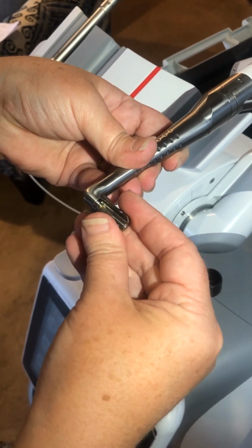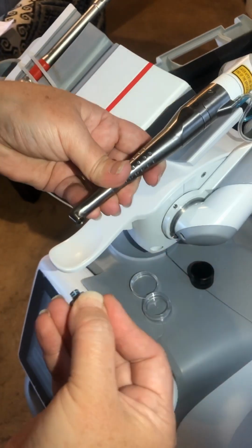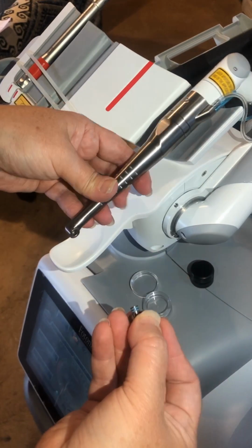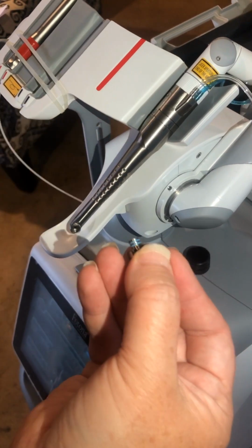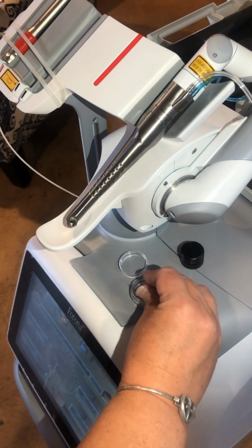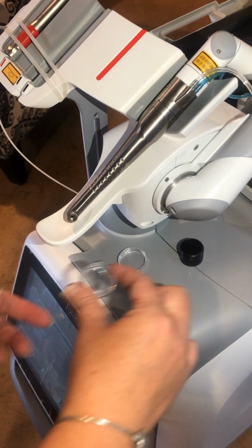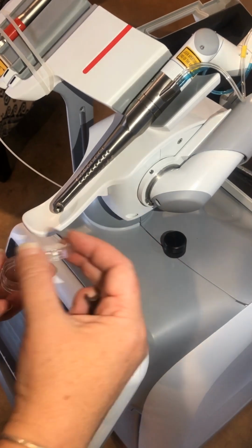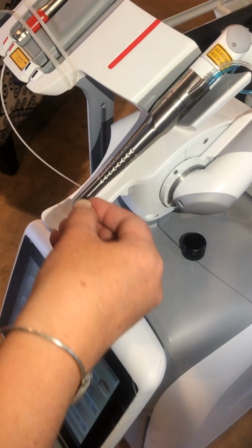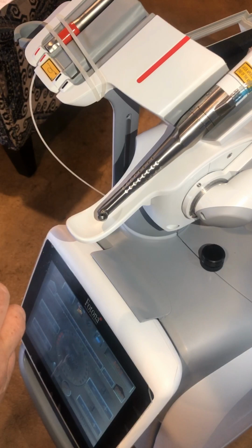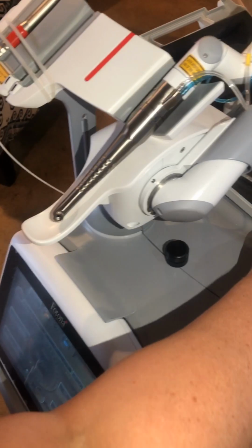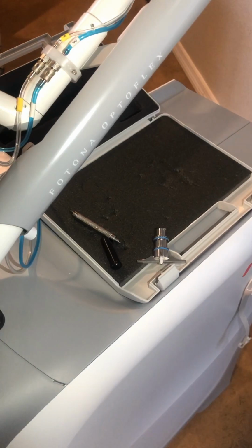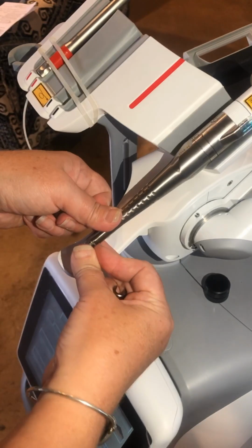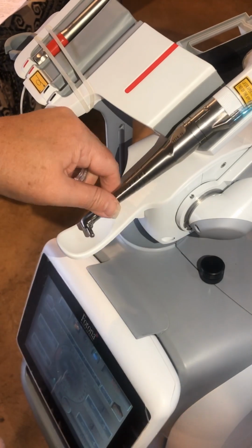Okay, they do make a tip carousel which will hold many tips, but you're going to need to know how to use this tip holder because once the tip is dirty, you can use this tip to remove it and dispense the next tip to do it and stay in a clean environment. Okay, when not in use, you want to put the plug back in the end to keep that sealed and protected.